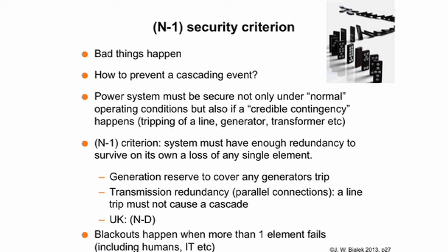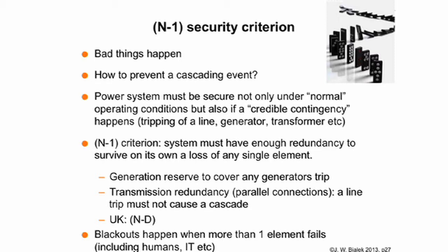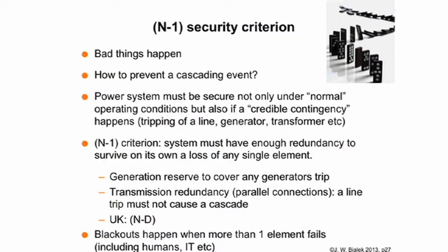They have a number of parallel connections, a number of paths to get you from A to B, because if one line trips, the other parallel transmission lines may carry the load, and of course the system must be run so that those other parallel lines will not be overloaded. In this country, actually, it's not n-1, it's called n-d, d for double, because on transmission towers we have two transmission lines running in parallel to two different locations depending on configuration. So the idea is if lightning strikes, for example, it will bring down two lines, so that's why it's called double. Generally speaking, if we're talking about underlying reasons, blackouts happen when more than one element fails.